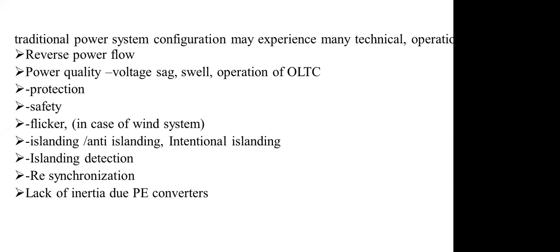Another issue is the lack of inertia, leading to faults. When you have a PV system, a PMSG-based wind system, or a fuel cell, you don't have any inertia. In a traditional power system, we have a huge turbine and a rotor running, which acts as temporary energy storage. If any load is removed or increased, that inertia takes care of it for a moment until the input is properly maintained. But in the case of power electronic devices, that facility is not there.